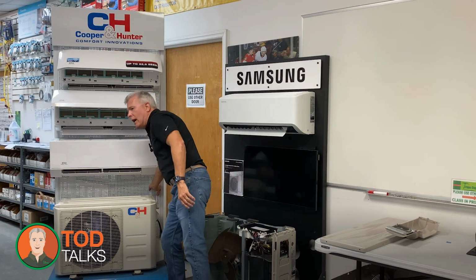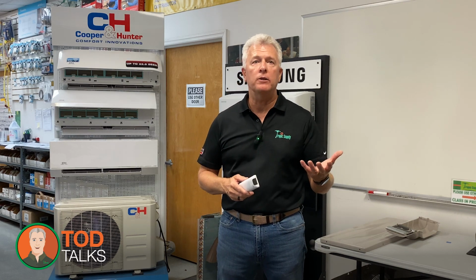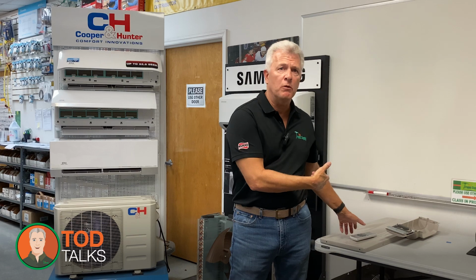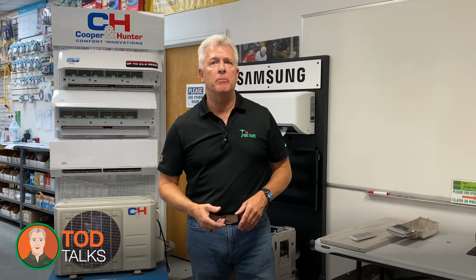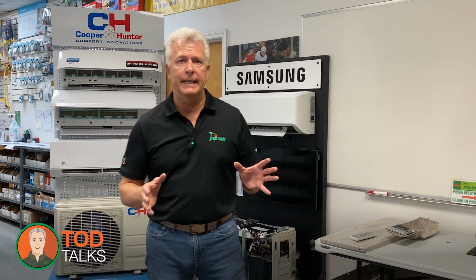Now, when it comes to controlling these systems, forget about the old R, G, Y, W terminals that you see on your thermostat. Mini splits don't use them. They're all about wired or remote controllers that send signals in a different way, either through shielded wires or infrared remotes. And if you're replacing a remote, it's usually a plug-and-play process with no extra programming needed.